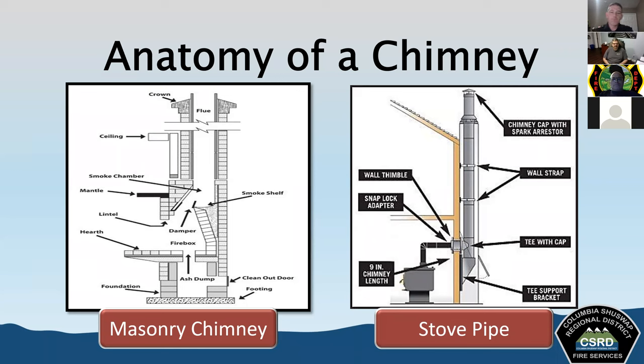So again, the majority of these chimney liners are made from aluminum, stainless steel, or the clay tiles that I was talking about. In other cases, you might find a poured in place masonry. A clean liner that's in good repair will efficiently vent the smoke and toxins out of the firebox and into the outside air. But damaged liners can lead to chimney fires and the decomposition of the bricks and mortar that make up the chimney. Damaged liners are also more likely to hold buildups of creosote, which can ignite and start a fire.